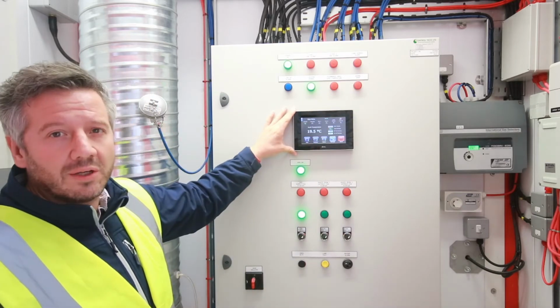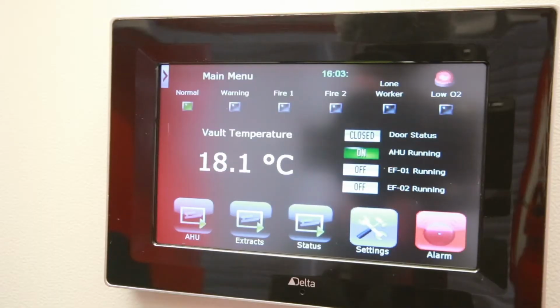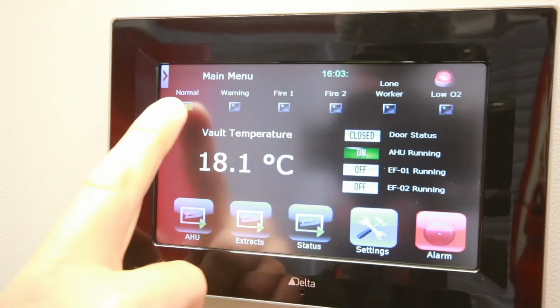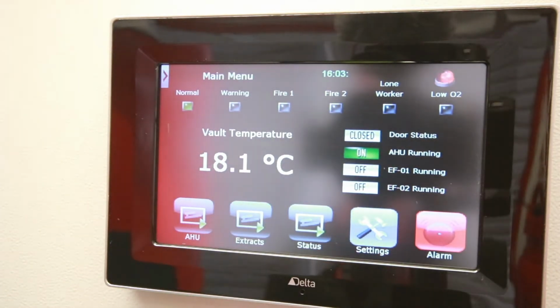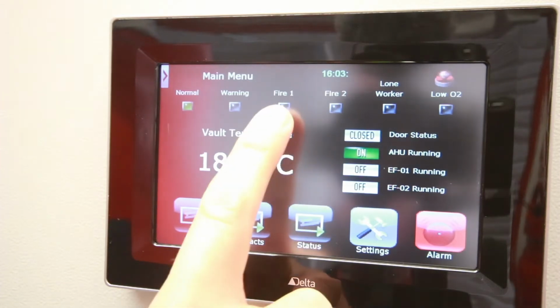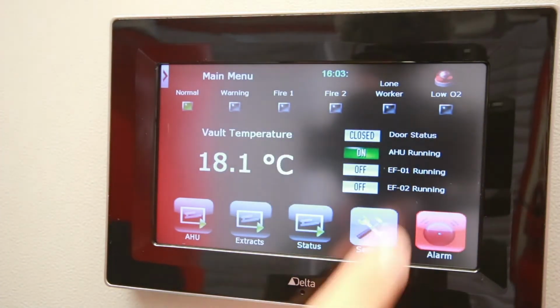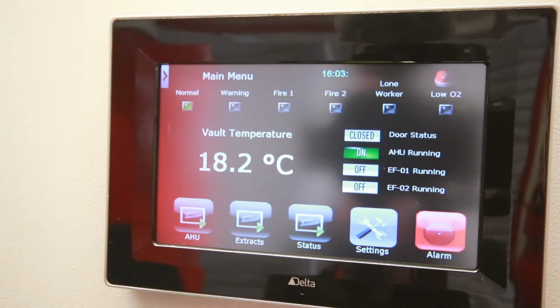Below we have the Delta controller, which is the brains of the operation. So here we have the Delta controller that's used to control all our air handling systems on our Chemstore Firevaults. And I'll lead you through some of the key features. At the top, we have our main menu, our bank of status indicators. This indicates normal working condition. This is our general warning common fault alarm. With this store, we've got two fire alarms, stage 1 and stage 2. We have a lone worker alarm and a low O2 in our plant room alarm.